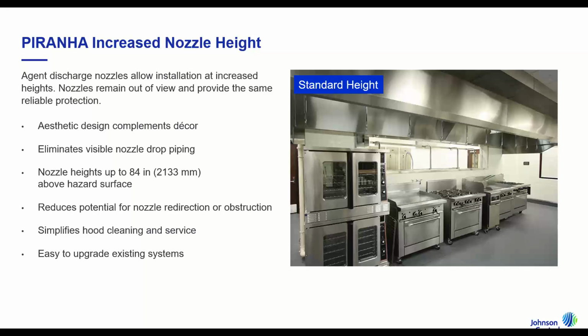So Piranha increased nozzle height. This was the one that I touched on. And this can go very high so that the nozzles are not visible to the cook. In some instances in restaurants or cooking facilities, they will not want the nozzles to be seen as it might be an open environment. So it's very aesthetically pleasing for those applications. The nozzles can go up to 84 inches above the hazard surface, again, also equating to 10 foot above the finished floor. It reduces the risk of any type of nozzle redirection or obstruction. So no accidental hanging of things on the nozzle drops, no pushing them out of the way, none of that as far as a risk.